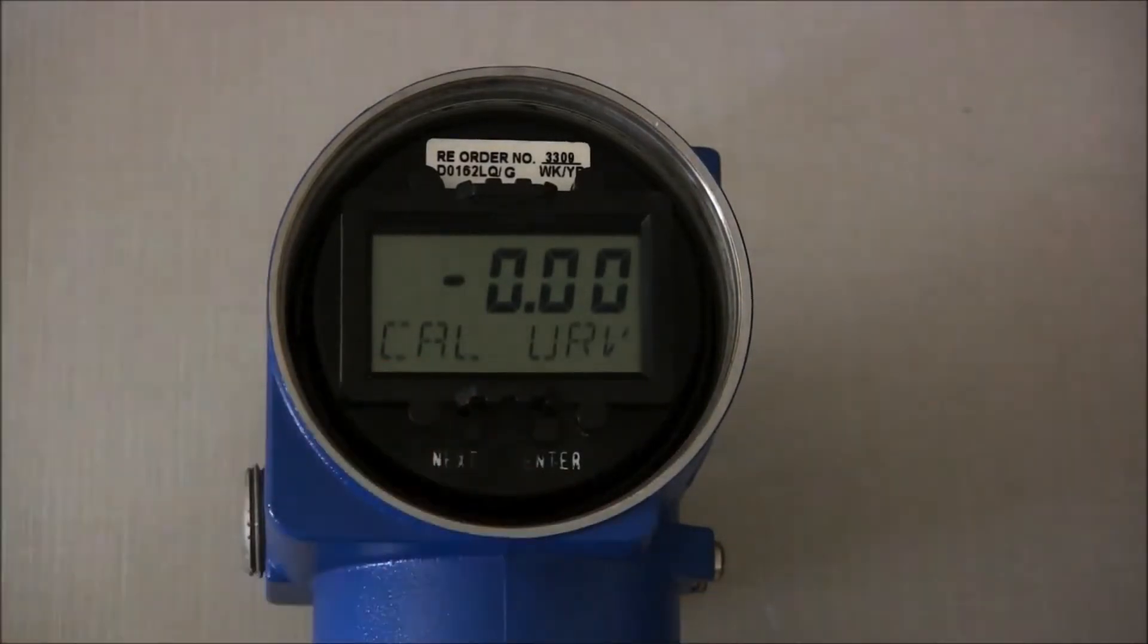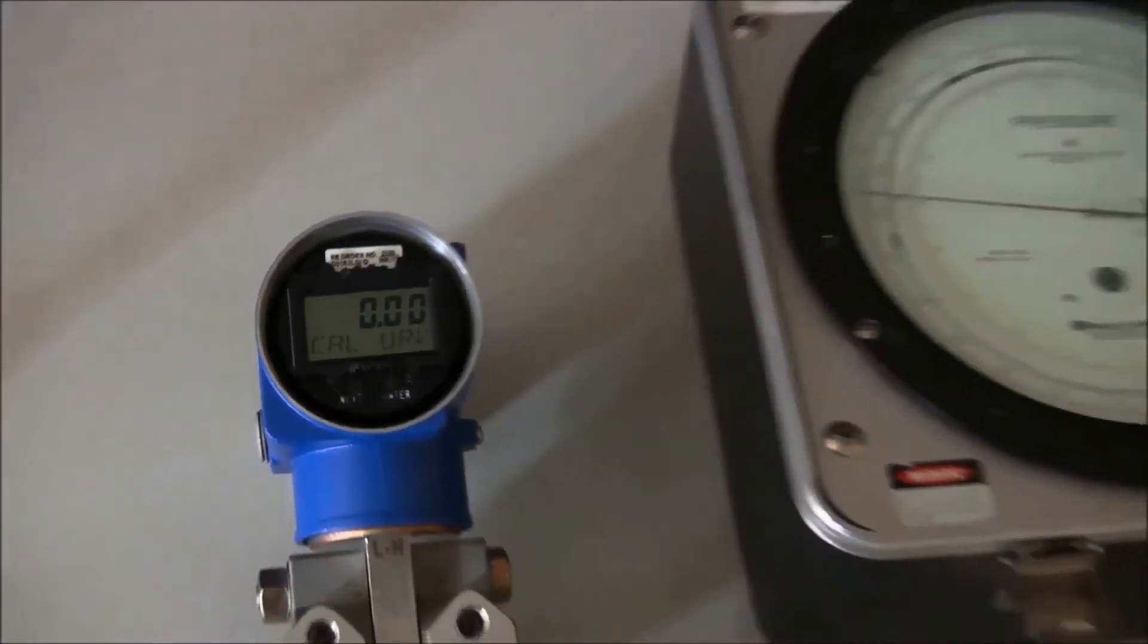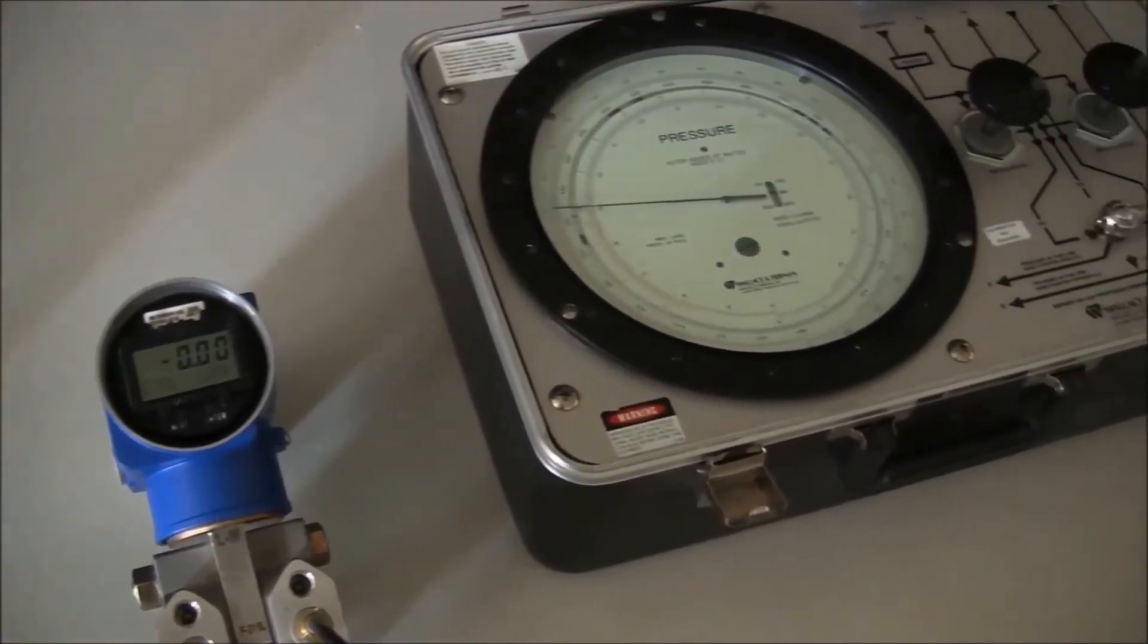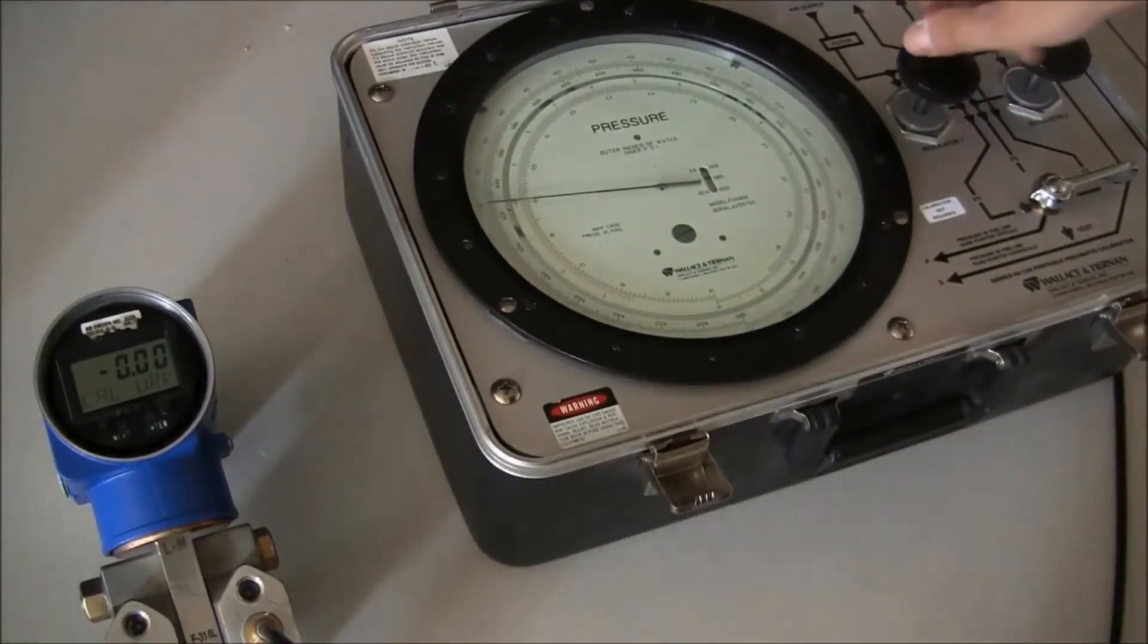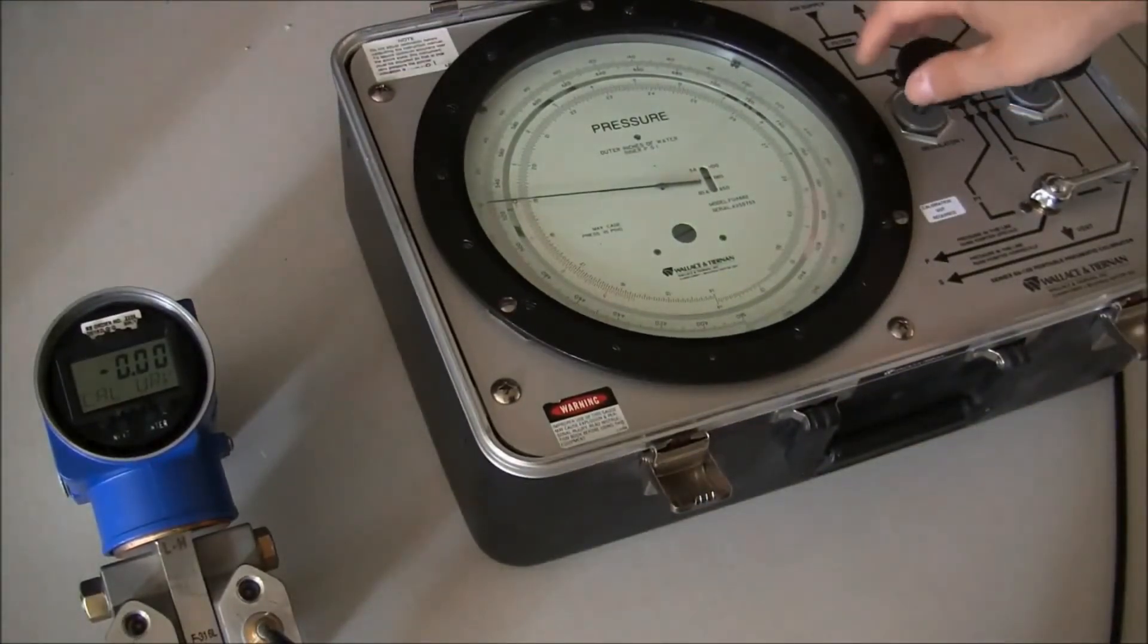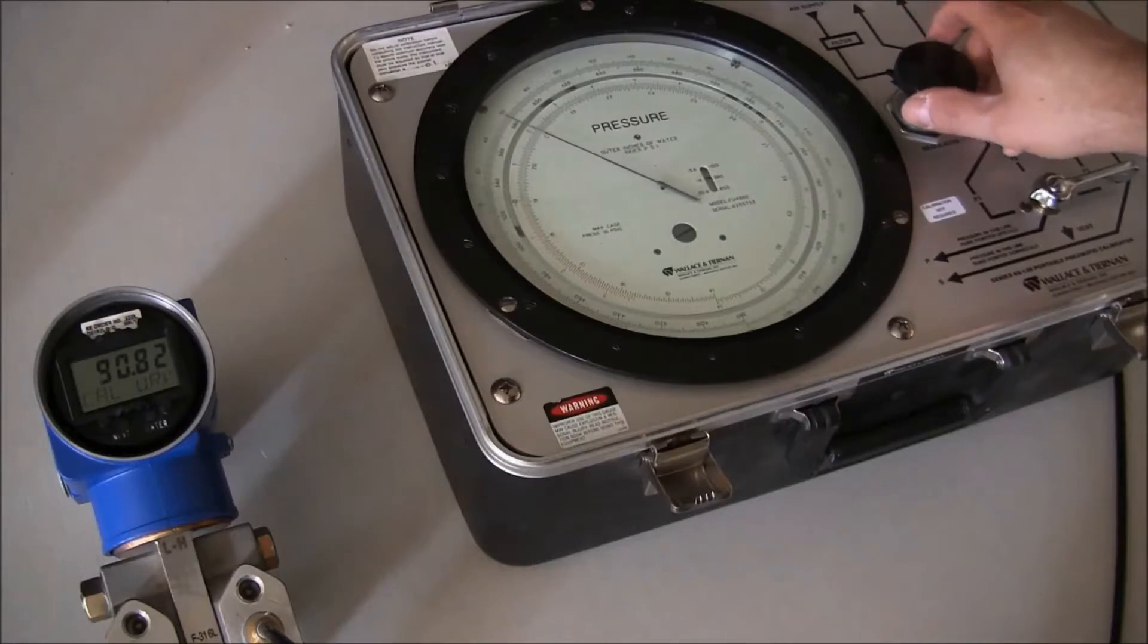Press Next and CalURV will be displayed. At this point, we need to apply the upper range value pressure to the transmitter. In our specific scenario, this would be 100 inches of water.